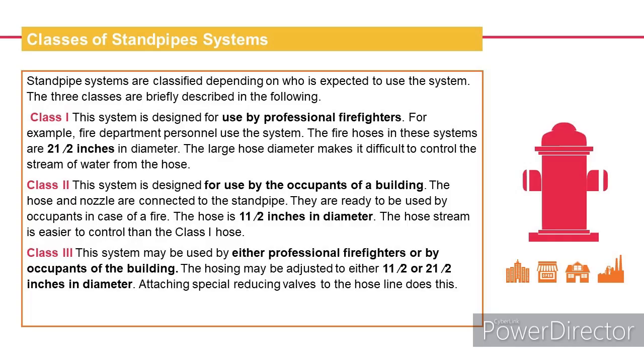Now here are the classifications of standpipe systems. Standpipe systems are classified depending on who is expected to use the system. The three classes are briefly described in the following. Class I. This system is designed for use by professional firefighters. For example, fire department personnel use the system. The fire hoses in these systems are 2 1/2 inches in diameter. The large hose diameter makes it difficult to control the stream of water from the hose.